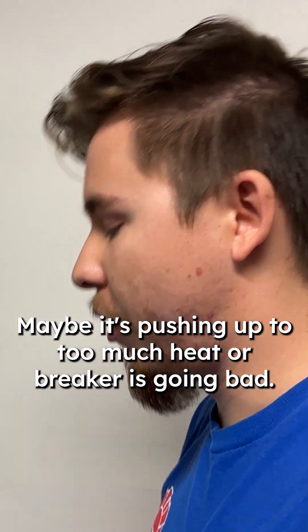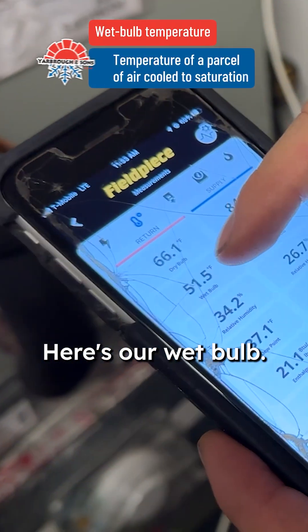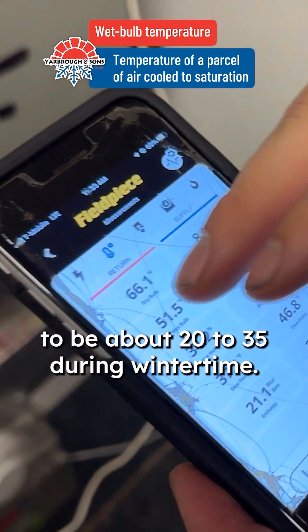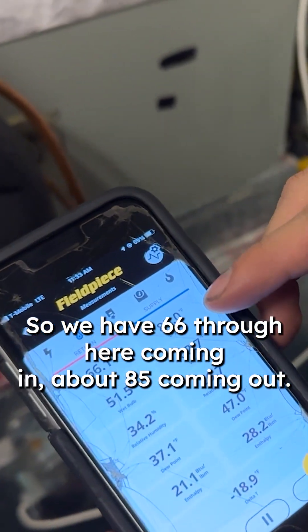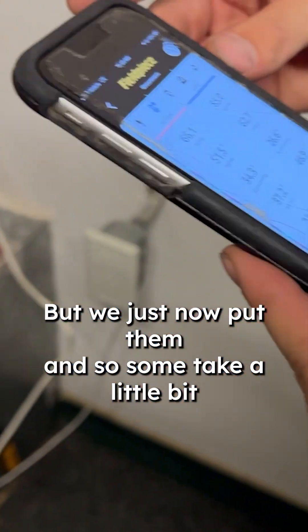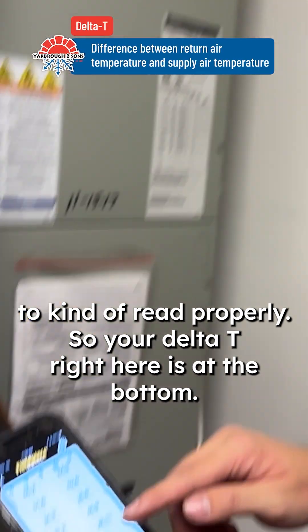So that's when we start diagnosing the heat strip — maybe the heat breaker is going bad. We just gotta wait now, let the heat rise up. The temperature split will show us our wet bulb, our humidity, our dew point. We usually want that range to be about 20 to 35 during wintertime. We've got 66 degrees coming in and about 85 coming out, but we just put them in so it's gonna take a little bit to run properly.